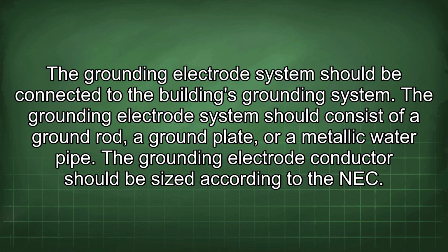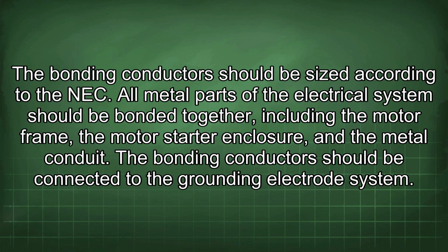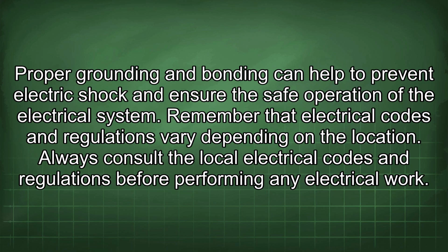The grounding electrode system should consist of a ground rod, a ground plate, or a metallic water pipe. The grounding electrode conductor should be sized according to the NEC. The bonding conductors should be sized according to the NEC. All metal parts of the electrical system should be bonded together, including the motor frame, the motor starter enclosure, and the metal conduit. The bonding conductors should be connected to the grounding electrode system. Proper grounding and bonding can help to prevent electric shock and ensure the safe operation of the electrical system.